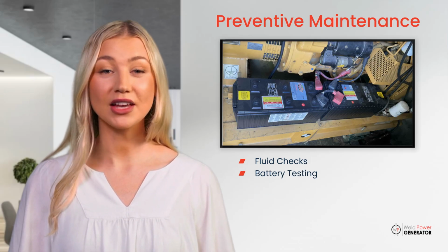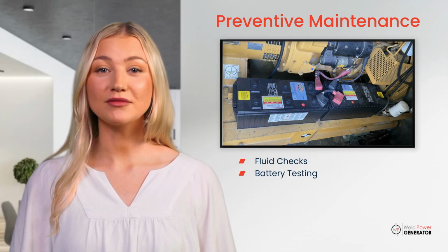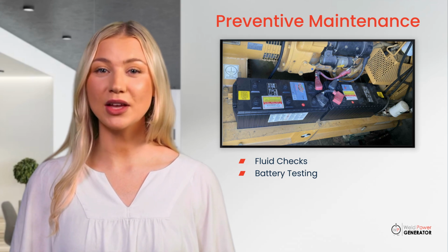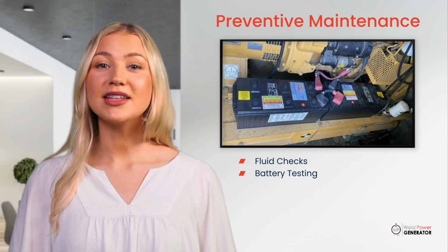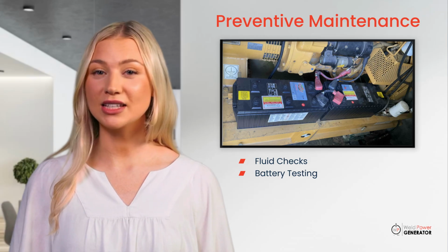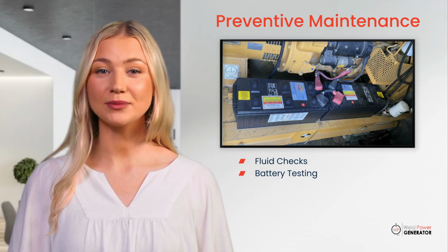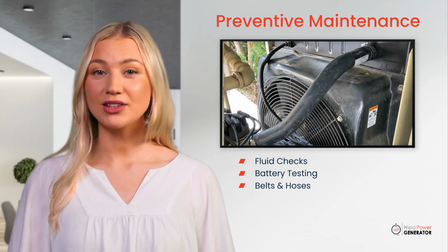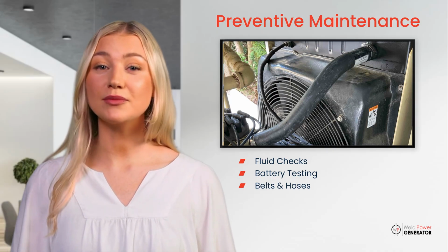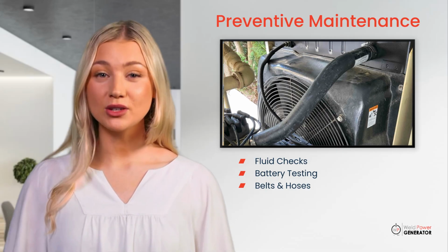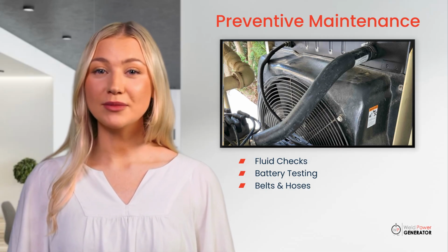Battery testing. Generator batteries are a leading cause of failure during actual emergencies. Test batteries at every PM visit and replace them proactively, typically every 2-3 years. Belts and hoses, inspect for cracking, fraying, or tension issues. These are inexpensive components whose failure can stop an engine cold.